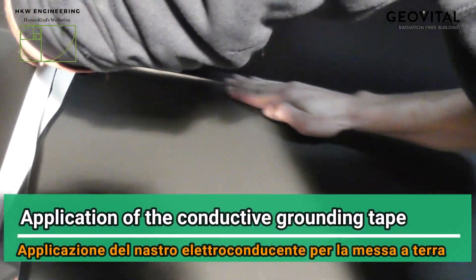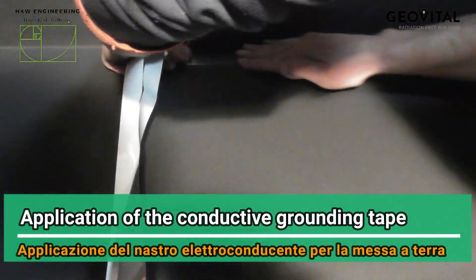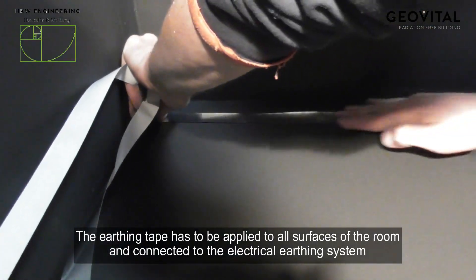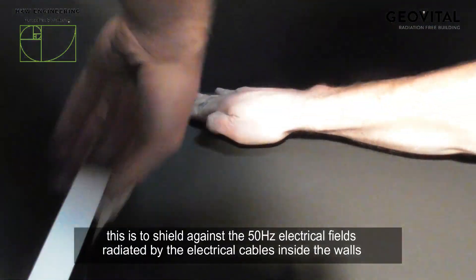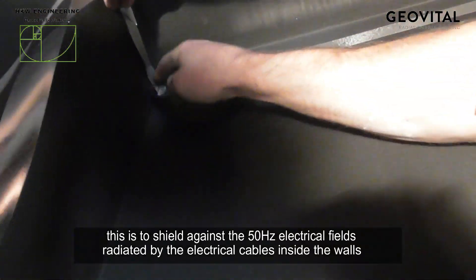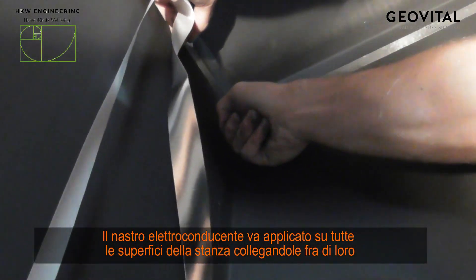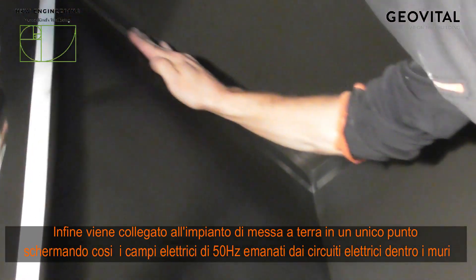After the first coat of T98 shielding paint, you should proceed with the application of the conductive grounding tape. This has to be applied to all of the surfaces in the room — walls and ceiling included — to shield against the 50 hertz electrical fields that are radiated by the cables inside the walls. The shielding grounding tape should be connected to the earthing electrical system at one single point.